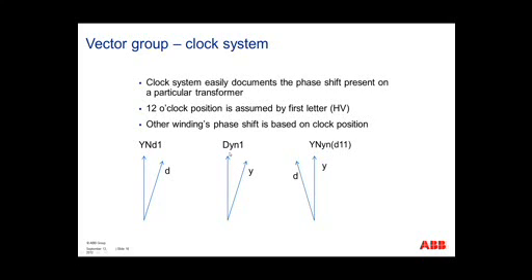Second example, we have a Delta-wye connected transformer, where the high side being a capital D is put on the 12 o'clock position of the clock. The Y connection is at the 1 o'clock position. We have 30 degrees, where the low side lags the high side by 30 degrees.